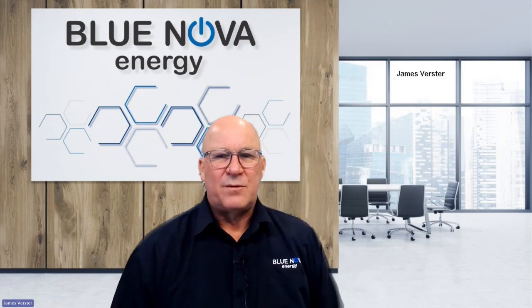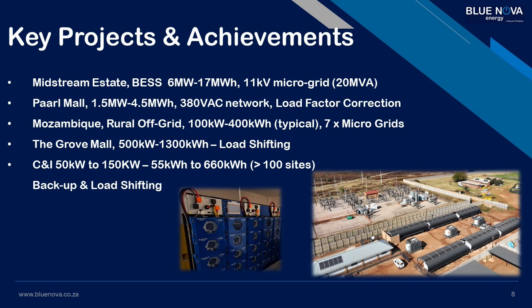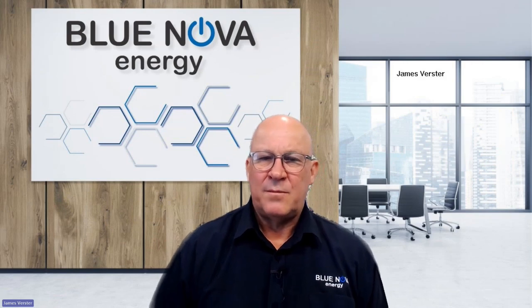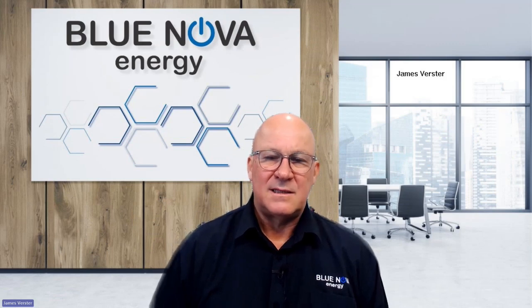We look at some of our achievements that we're really proud of. The largest public-owned battery energy storage system at Midstream Estate in Midrand, 6 megawatt by about 17 megawatt hours. And that system is primarily a backup system for power interruptions, but now, with very little load shedding, it acts as a load shifter, saving the estate lots of money because of the price arbitrage opportunity. Paarl Mall load factor correction system, also saving the mall a lot of money by optimizing the demand between the peak demand and the lowest demand in any cycle.